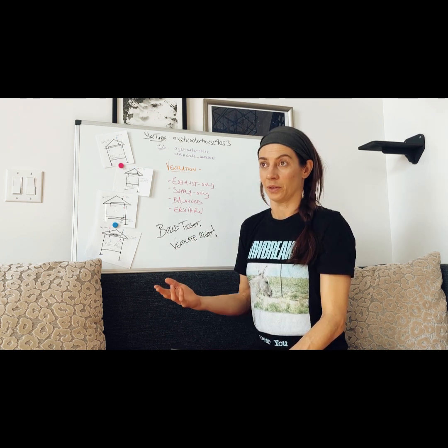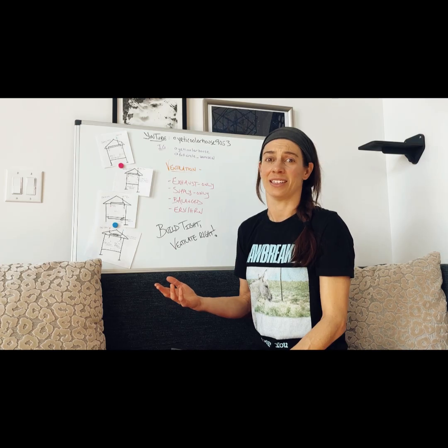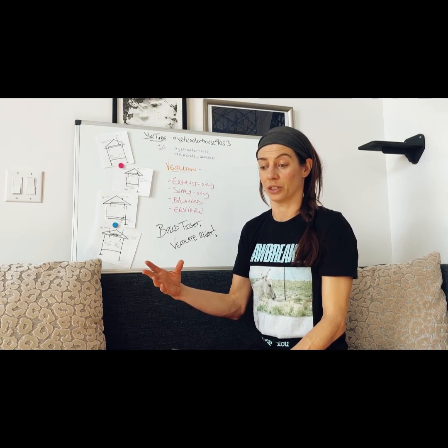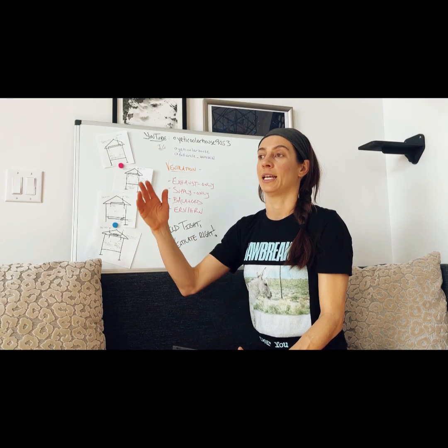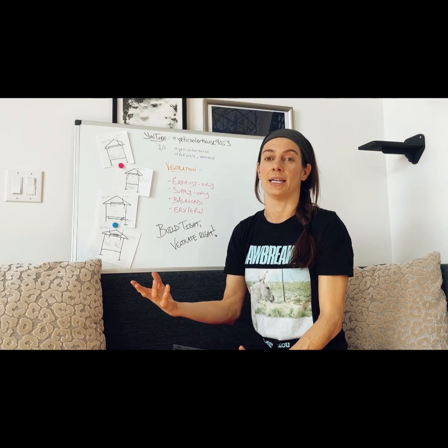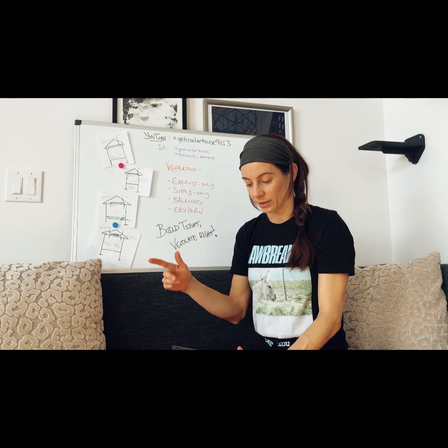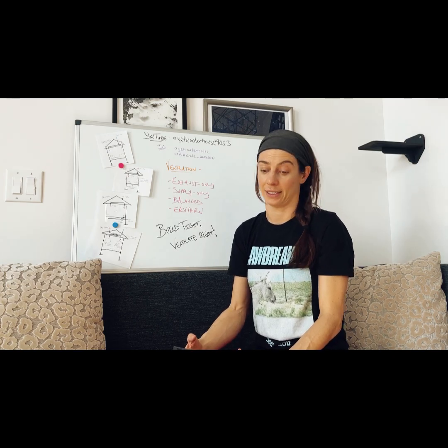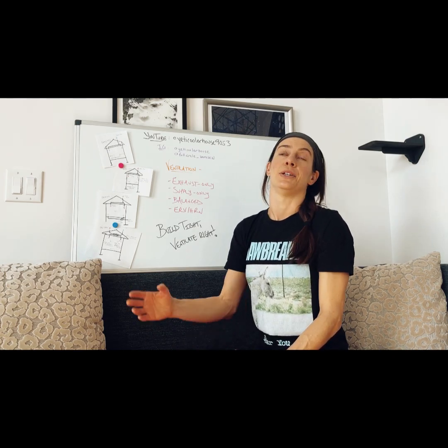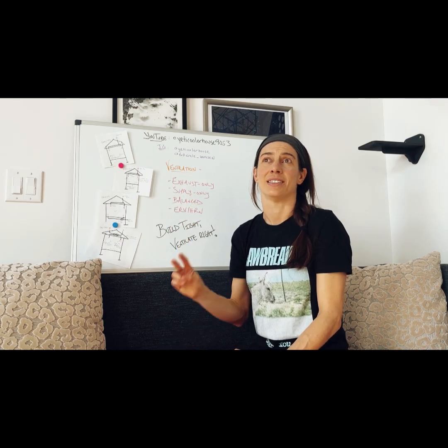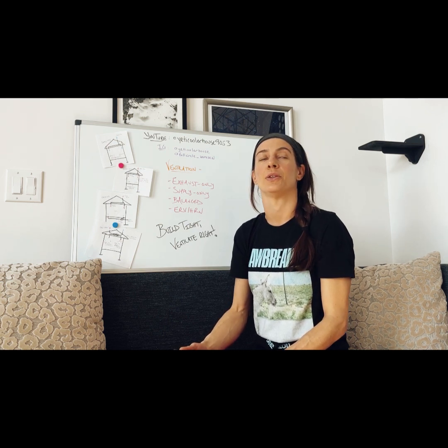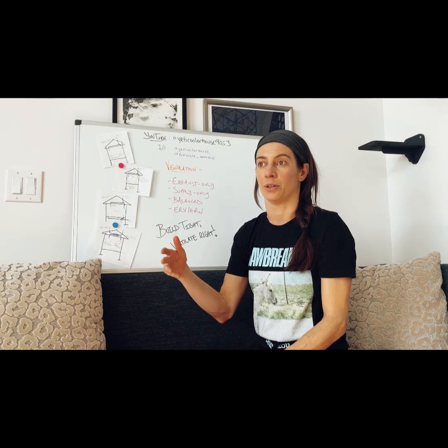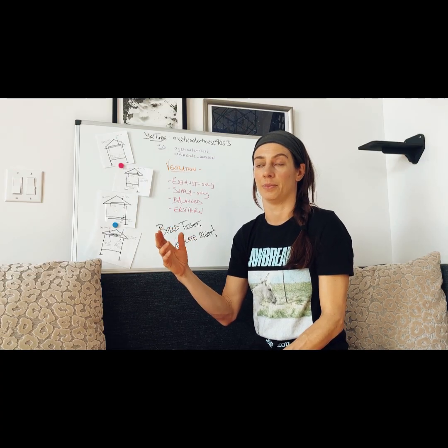And that's typically okay, but really you're just exhausting all that air that you just worked hard to condition to either heat or cool, and now you're exhausting it outside, and that air has to be replaced by other air that needs to be reheated or recooled. And that incoming air is typically not filtered and not controlled. It's coming in through the cracks of your house is the thought process behind this. And if your system is not running continuously, you'll have to have a damper on the exterior so you don't just have a hole in your now airtight home. So that's just another aspect of this.